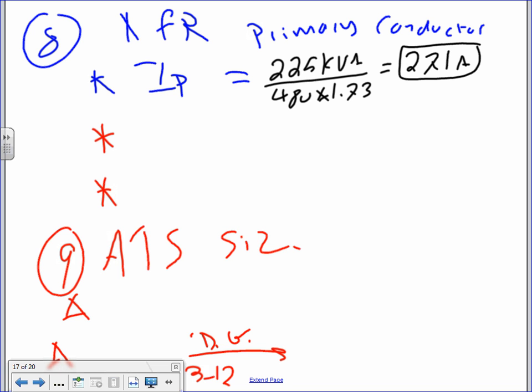Wouldn't you have to multiply it by 1,000 again and then divide it by 1.73 times the voltage? Which step are you doing? Number 8? Yeah, you have to multiply the top by 1,000. 225K times 1,000 divided by this. Oh, no, I thought you meant the total kVA, like 225,000 times 1,000 again. No. 225K becomes 225,000 divided by that number.